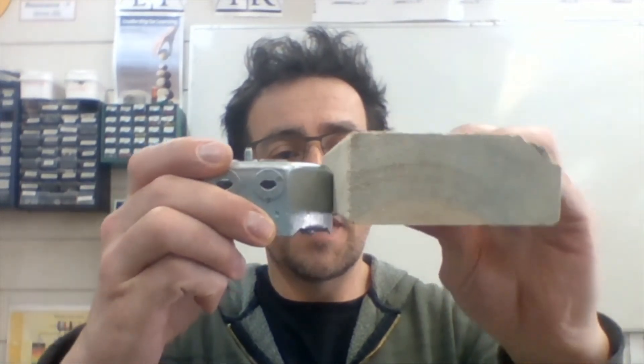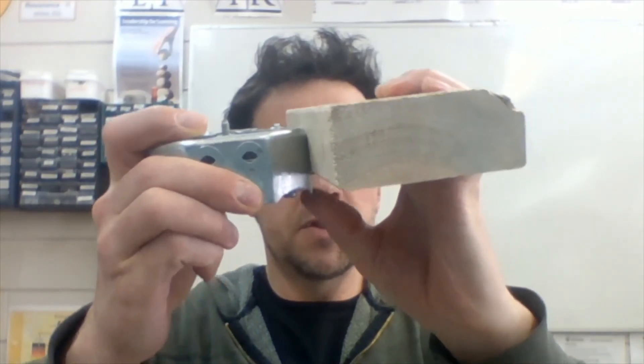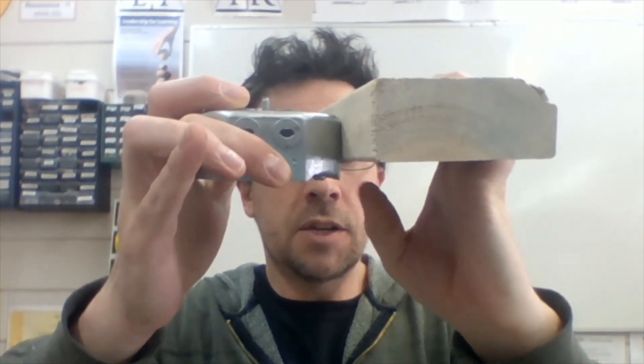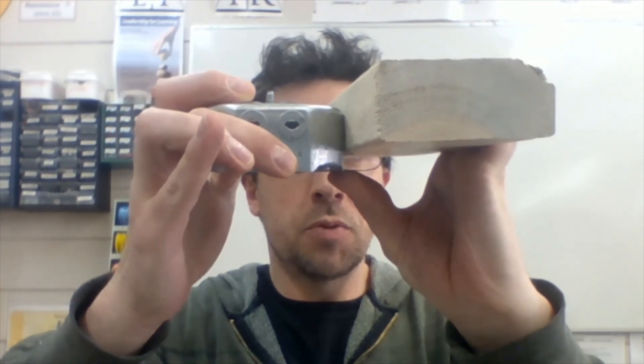This style of octagon box does not have that and inside of here, if I was to attach this to the ceiling, there's really only one, two spots that I can attach a screw onto. Both octagon boxes do have these spacers here. The point of the spacers is so that it keeps about half an inch difference for when I attach the drywall. The drywall would sit flush with the bottom of the box there.